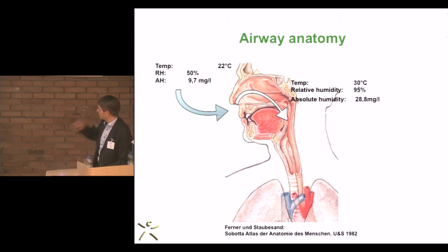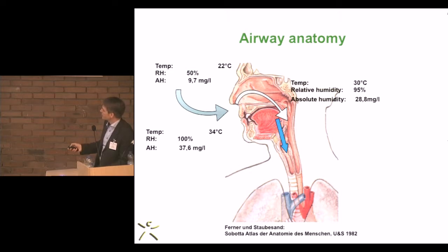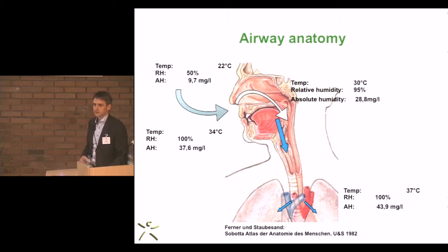And then once the air enters the nasal cavity, the relative humidity very rapidly goes up to 95%. You see how effective this equipment we have is. And it's already heated up to 30 degrees. However, the absolute humidity here is only 28 and far from what we want to reach. Once we go down the tracheal lumen, we increase the relative humidity very rapidly to 100%, increase the temperature, and down at the bifurcation, we reach relative humidity of 100%, equaling this 44 milligrams per liter at 37 degrees Celsius. So this is what we want to achieve once we have our baby intubated.